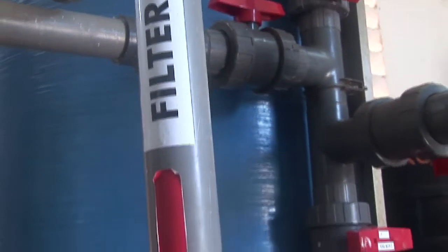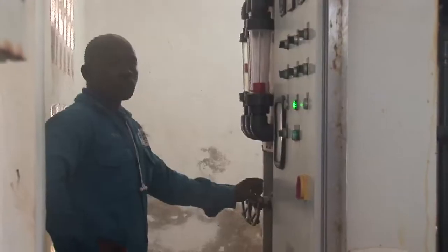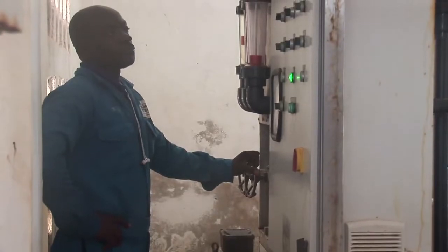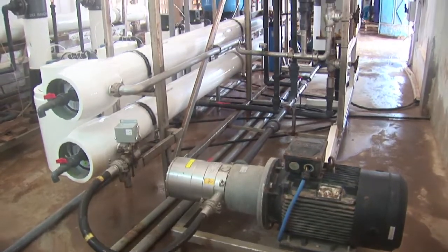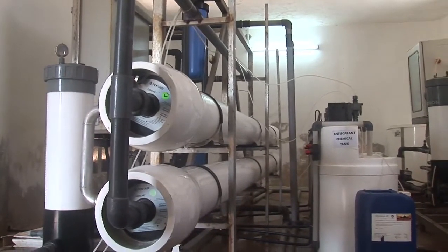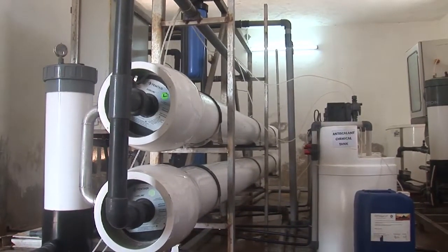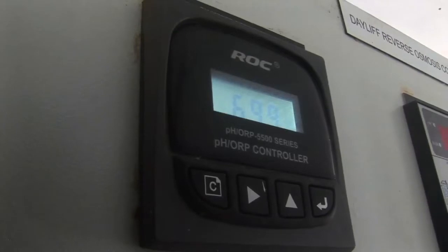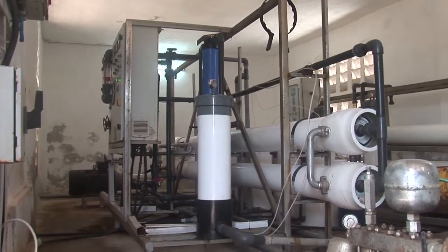We have the pre-filtration, which is a sediment filter, and it removes or filters light particles so that they will not clog on the membranes. For RO to produce fresh water from salt water, an applied pressure from the high pressure pump is used to overcome the osmotic pressure and push water from high concentration of contaminants to low concentration. The contaminants are trapped out and only the pure water passes through, resulting in the cleanest possible water.